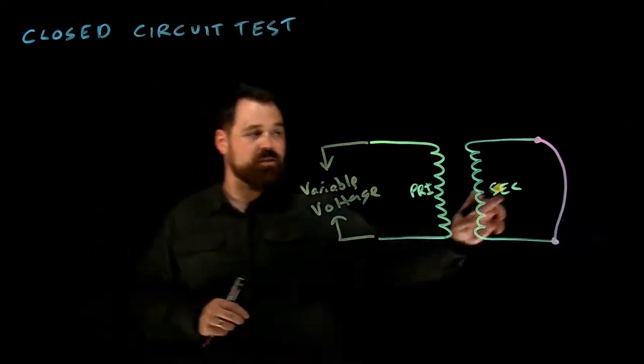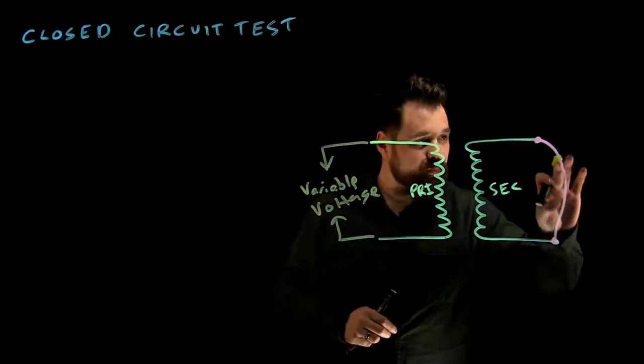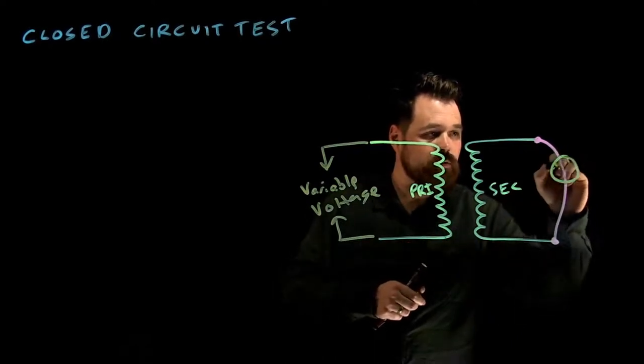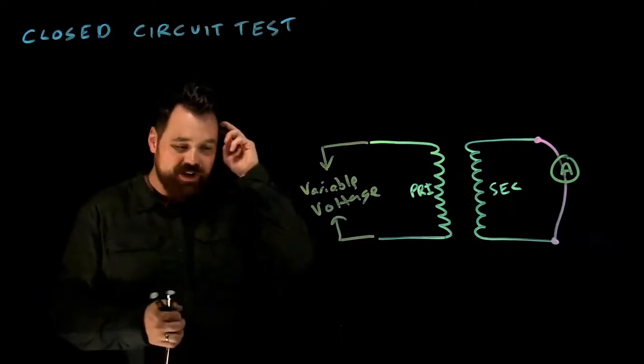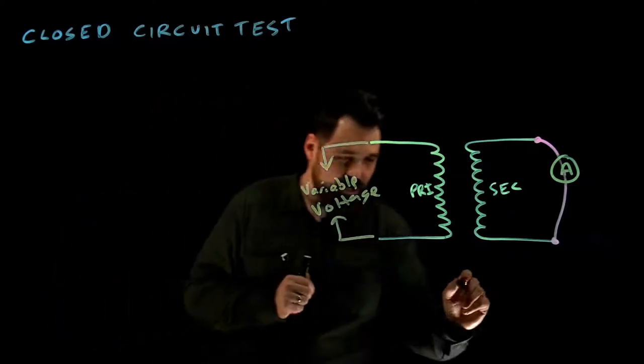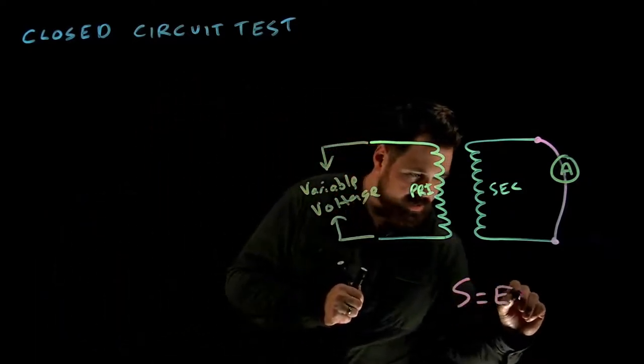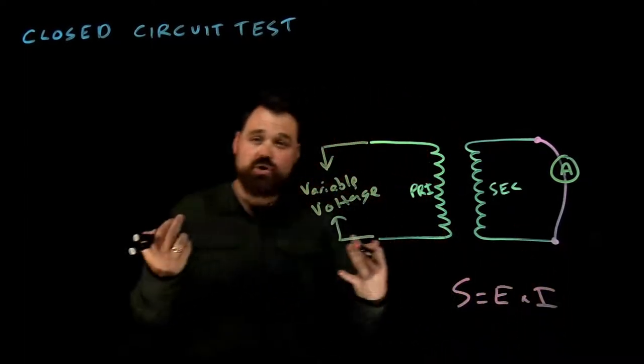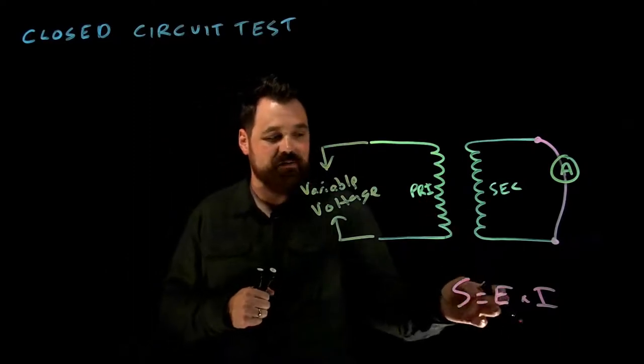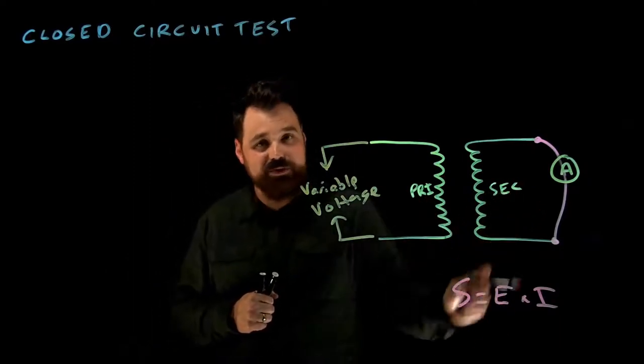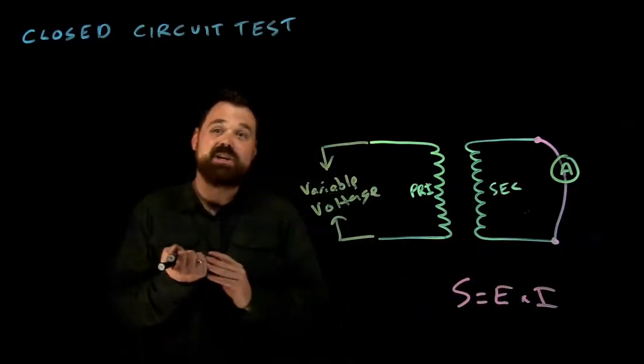Therefore, here on the secondary, we're going to put an ammeter. So we're going to calculate our rated secondary current. How we're going to do that is we're going to use S equals E times I. Of course, transposing, we take the apparent power of our transformer divided by the rated secondary voltage, which is going to give us the rated current.